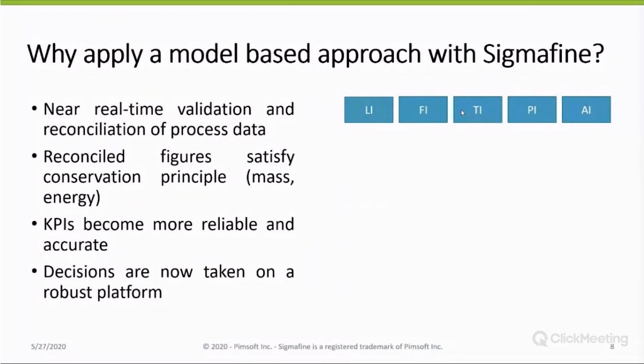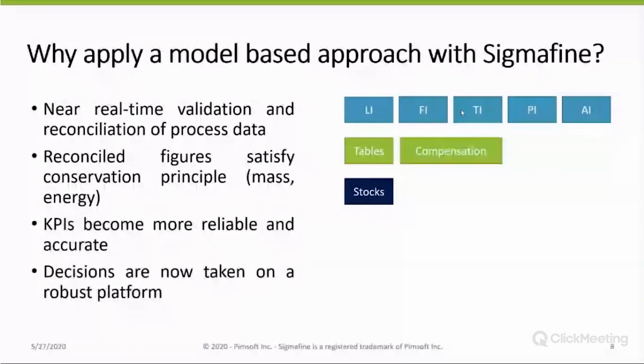Which parameters are we interested in? Level gauges, flow rates, temperatures, pressures, analyzers. For example, if we take a level and apply a strapping table or some geometry calculation, we can calculate the total inventory associated with it. Around flow rate, we can use temperature and pressure to apply compensation, and therefore evaluate the associated measured mass.